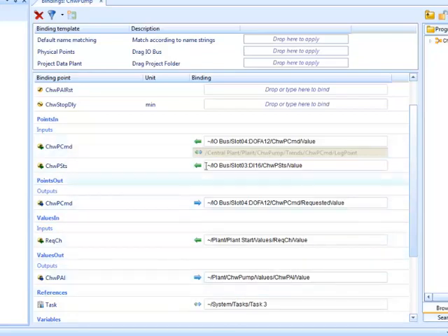So you start to see a lot of similarity. Focus on the programs. If you edit bindings on the program, you'll see the majority of the data flow that's going on within a subsystem. You might miss one or two pieces of data flowing, but if you jump around to some of the trends and alarms and schedules, you'll pick up any stray cats and dogs. But the program is the heart and soul of each subsystem. It's the traffic cop, if you will, data coming, data going. It's how you understand how all these objects are glued together.